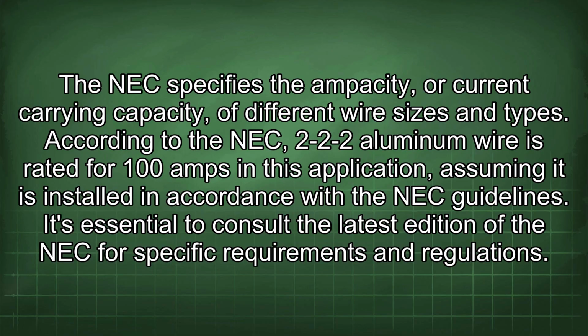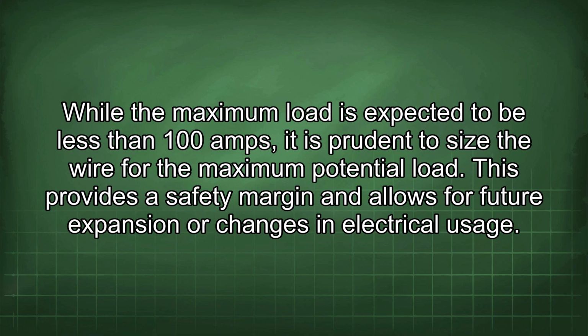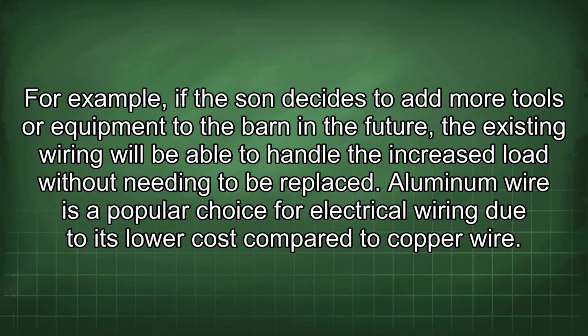It's essential to consult the latest edition of the NEC for specific requirements and regulations. While the maximum load is expected to be less than 100 amps, it is prudent to size the wire for the maximum potential load. This provides a safety margin and allows for future expansion or changes in electrical usage. For example, if the son decides to add more tools or equipment to the barn in the future, the existing wiring will be able to handle the increased load without needing to be replaced.